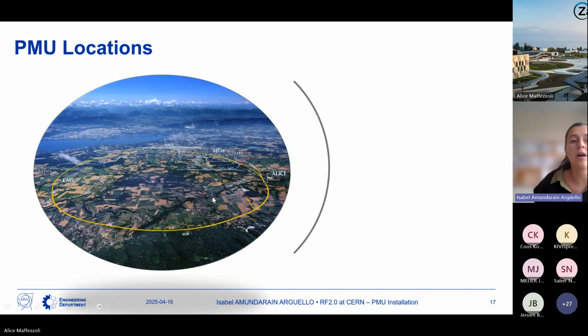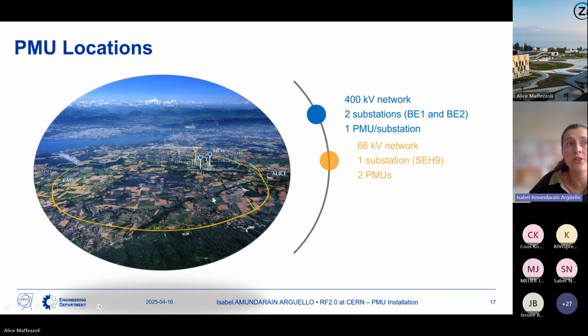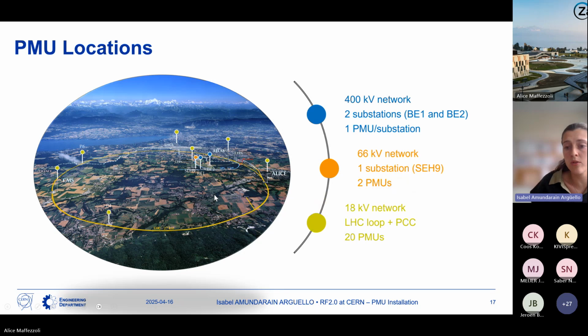Thank you. Focusing on the PMU installations at CERN, we installed a total of 24 PMUs: two in the 400 kilovolt network, two in the 66 kilovolt network, and the rest in the LHC loop, as well as another one in the computing center, with special focus on one of the experiments, ALICE, marked on the right, where a total of 9 PMUs were installed to monitor all the different types of loads.